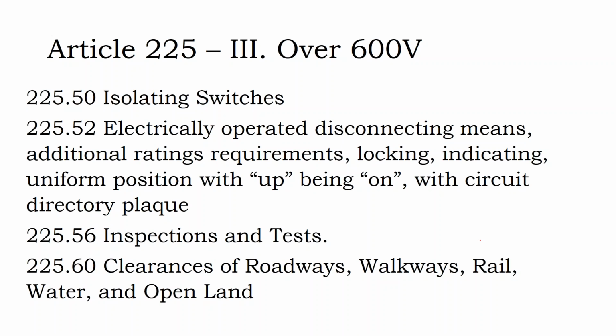Then we get into rules for circuits that are over 600 volts. So you may be getting into ground-mounted solar design, where you get into higher voltage systems, and sometimes in higher voltage systems, protection requirements drop out. That's usually because there are additional protection requirements elsewhere in code that make up for that simplicity whenever there is simplifying for going into higher voltage.